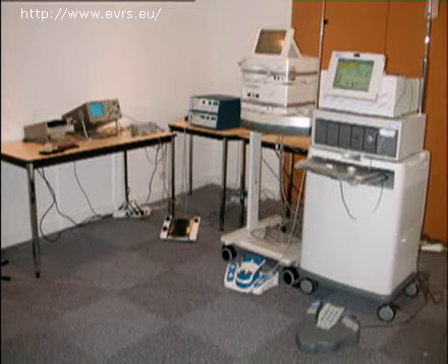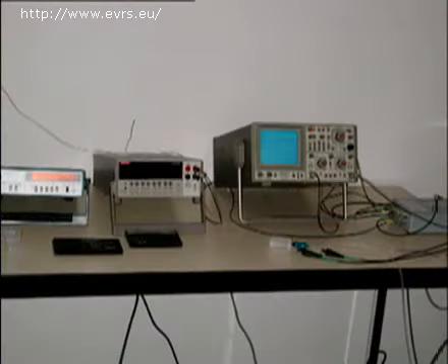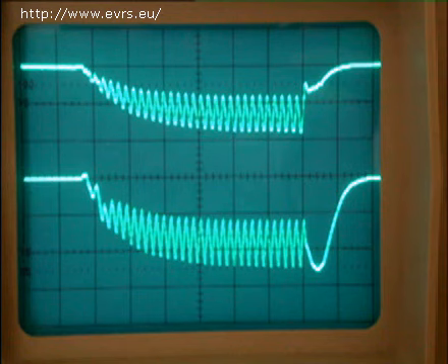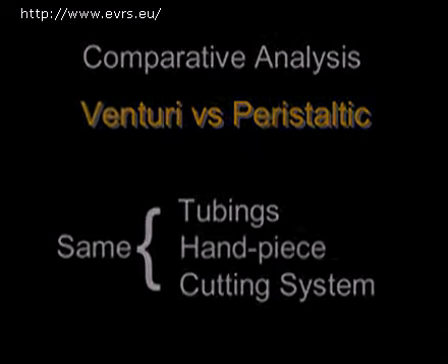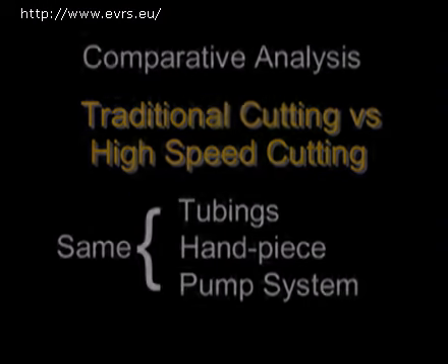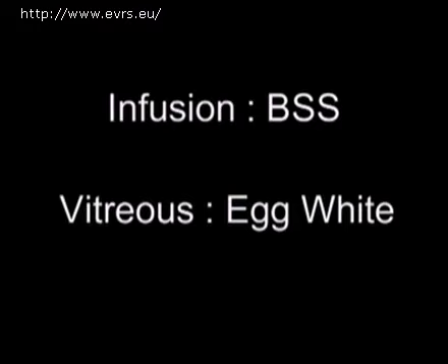These authors studied the performance of different machines by measuring the actual flow and actual depressions at the pump level. Pressure indicators at the test chamber level and at the exit of the handpiece permitted them to measure, with the help of very precise instruments, simultaneous pressure variations. To avoid all possible error in the comparative analysis of venturi vs. peristaltic or classical cutting vs. high speed, all other parameters were kept constant at each stage. The infusion liquid was BSS, and egg white was chosen due to its heterogeneous and viscoplastic characteristics that are similar to the vitreous.